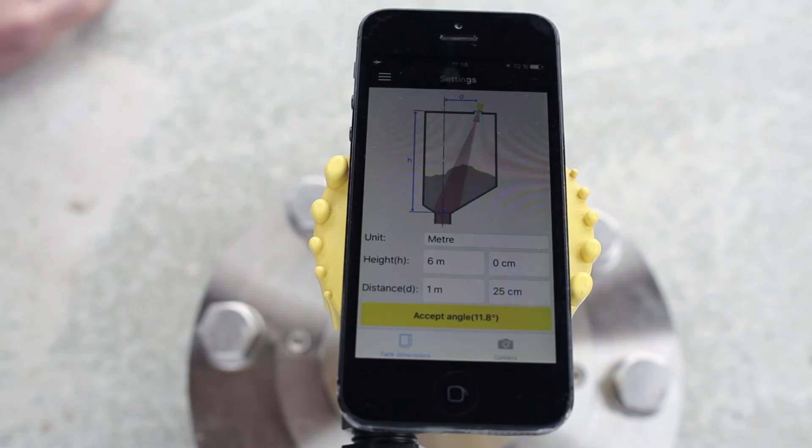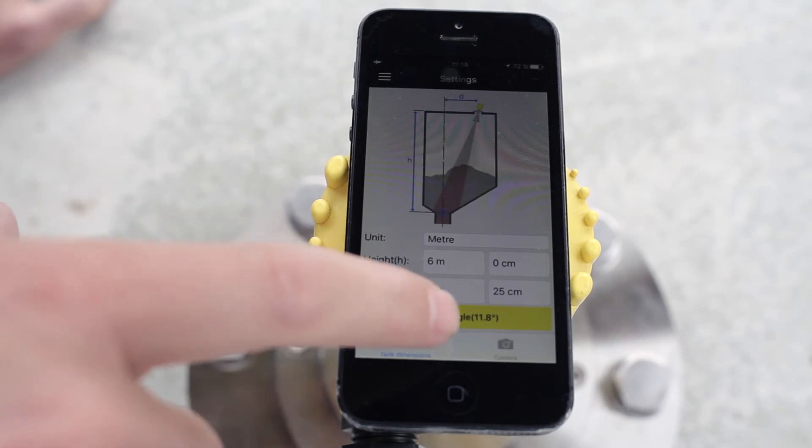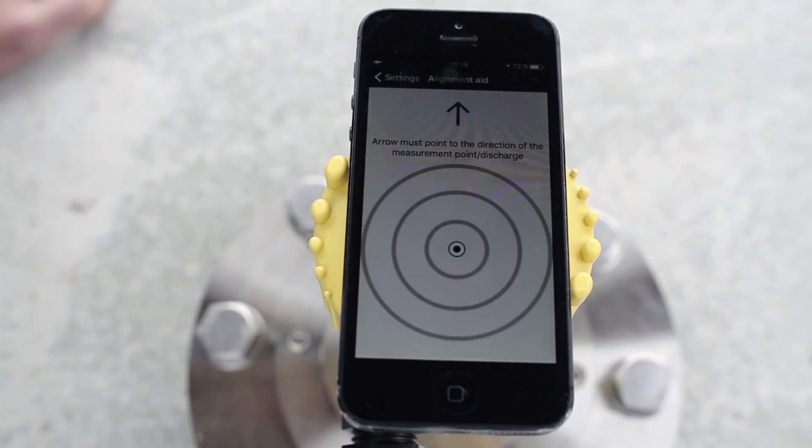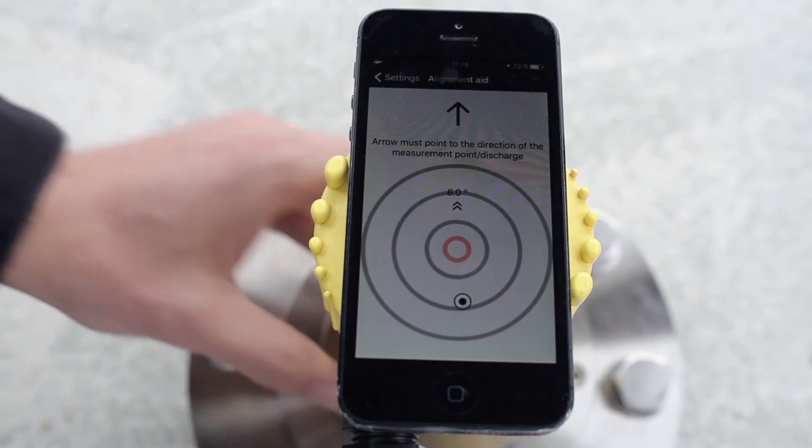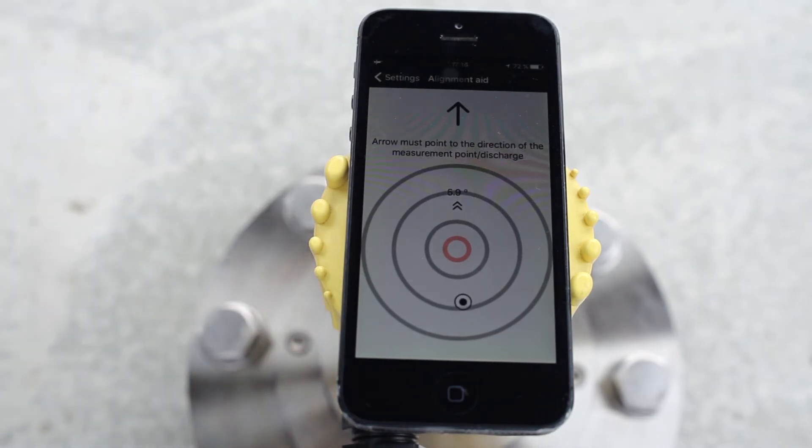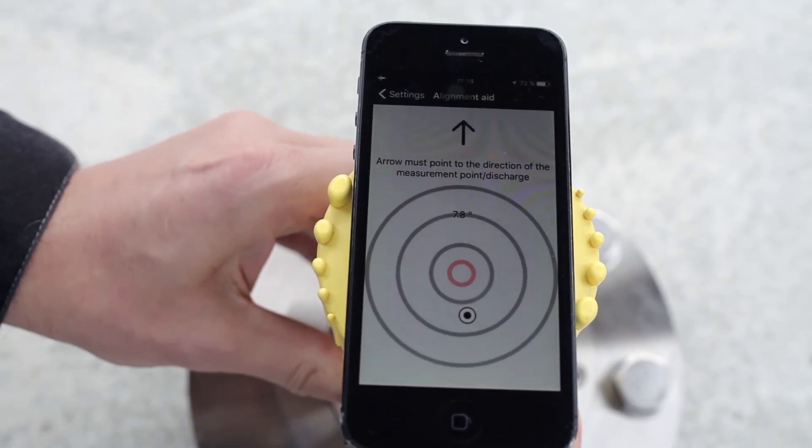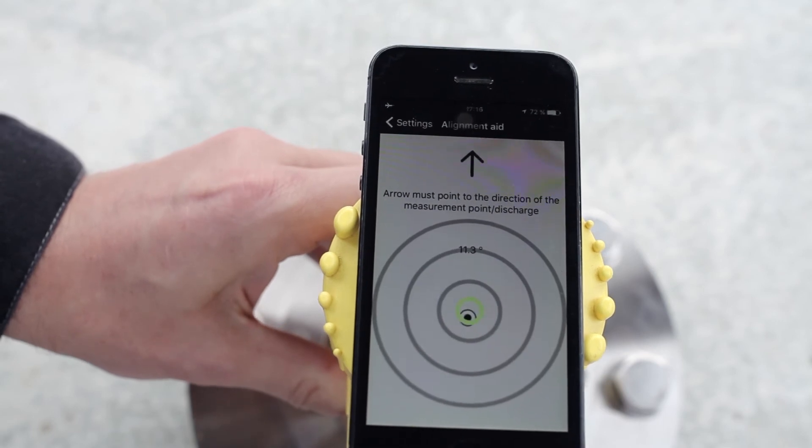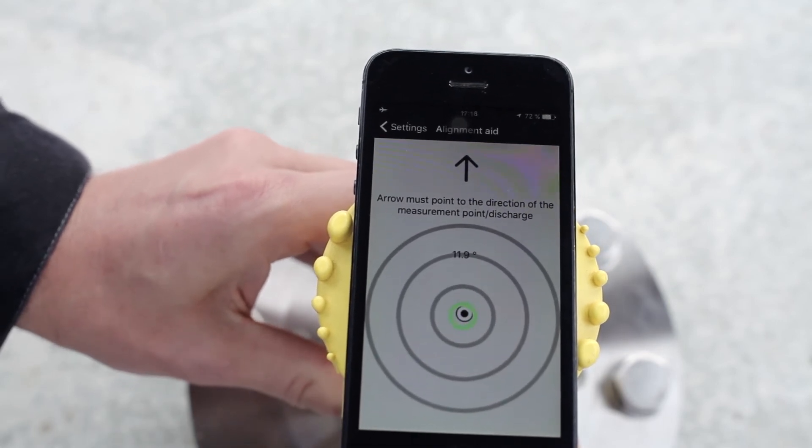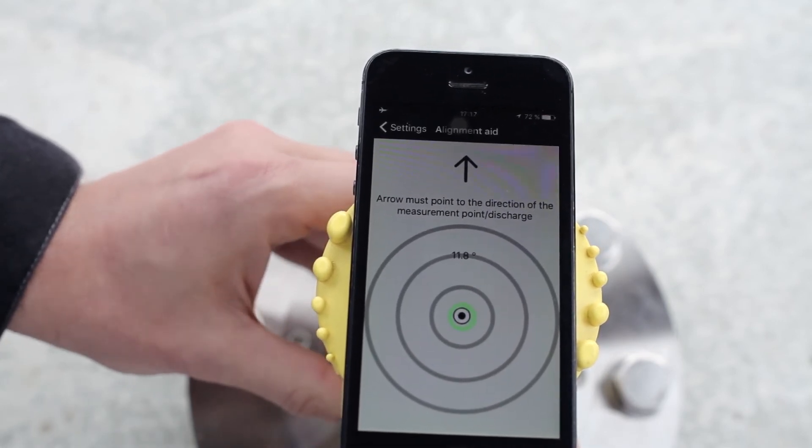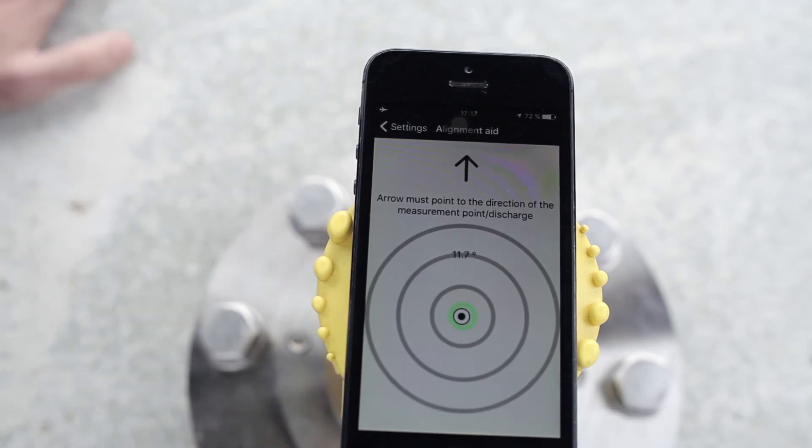With this information, the app is calculating an angle you see it here, and then you can just press accept angle and then you're in the alignment aid. Now you have to look that the arrow is pointing to the middle of the silo, and then you can align the sensor until it is in the goal and it's getting green. This is the perfect setting for the sensor. So fix the screws and the sensor is adjusted.